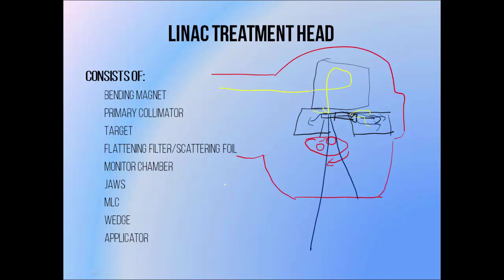The beam then passes through a monitor chamber, which is a radiation detector that allows us to determine how much radiation is leaving the treatment head. This allows us to choose a dose to deliver to our patient, and after the machine has measured a certain amount leaving the treatment head it will turn off. Beneath this we collimate or shape the field with a set of jaws or mobile radiation shields, and depending on the machine design we might also shape the field further with a multi-leaf collimator or an electron applicator.